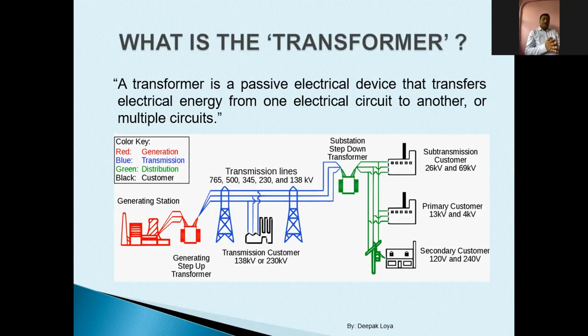But if I have a solar power plant, say a ground mounted solar plant of 1 megawatt, then my generating voltage may be in the range of 600 volts or 800 volts. Now I cannot use this 600 or 800 volts at my house. So to change the voltage level to connect to my circuit, I need a transformer. So a transformer transfers energy at different voltage levels. Sometimes I need to increase the voltage, and sometimes I need to decrease the voltage.